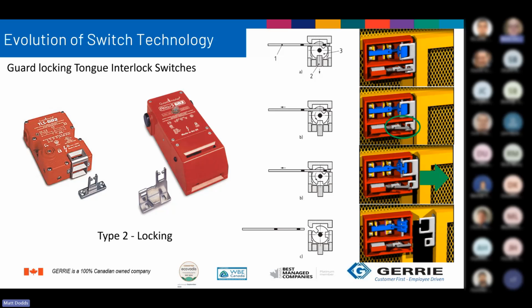So again, the main issue with any cam operated switch is damage to the actuator and/or damage to the cam mechanism from excessive force being applied to the switch when it's locked or when a door is slammed closed. Once during an on-site visit, I overheard one of the maintenance personnel say, "I need to go straighten the actuator on that machine again." So again, it's commonplace. But what can we do to overcome that?